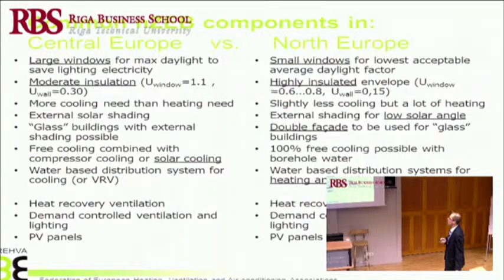Free cooling is needed in both climates to support compressor cooling, and in a cold climate you can even produce 100% of cooling energy, for example from borehole water. It's possible, but in Central European climate you still need compressors and something supporting the compressors. And water-based distribution systems are used especially for cooling in Central Europe, because there is a lot of cooling, and in our climate for both heating and cooling.